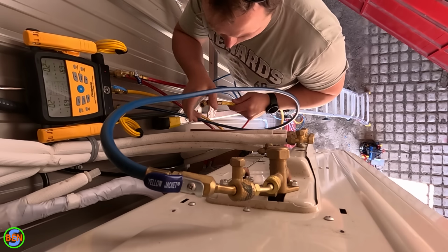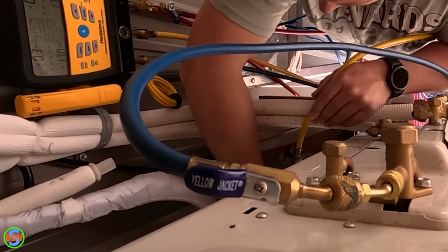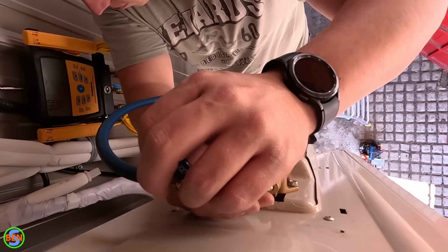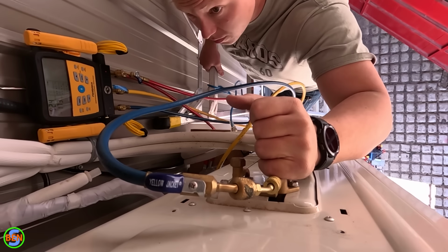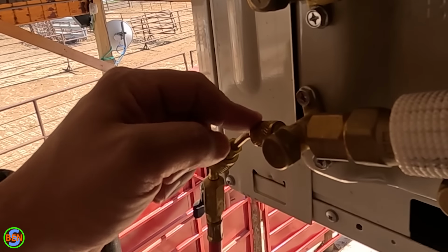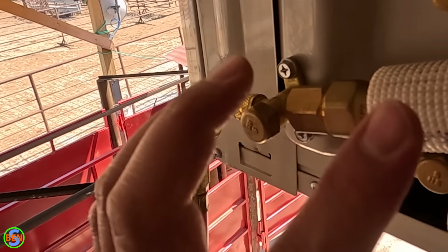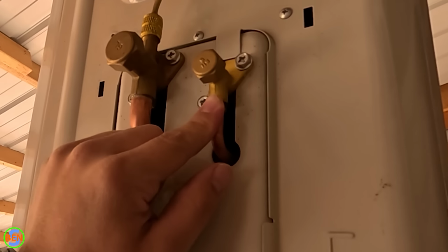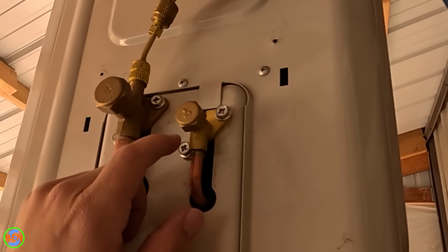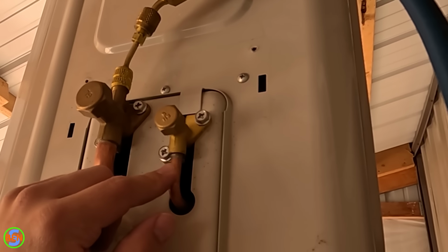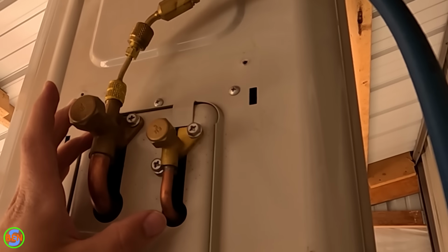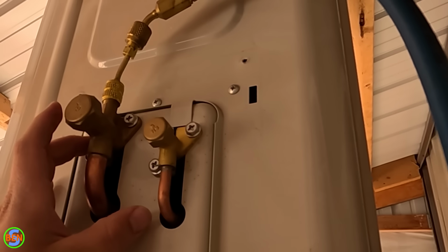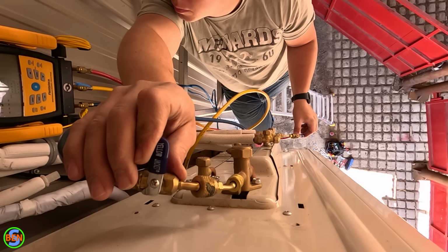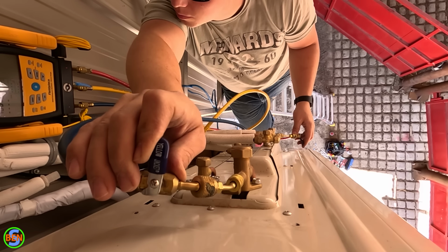So when you hook up your gauges, you're going to want to take the yellow hose and connect that to your vacuum pump. And then the blue and the red hose, the high and the low side, oftentimes you can connect both of those to a traditional system while you're pulling a vacuum. This one was set up more so to just pull a vacuum on the low side by itself, and we could have just done that with just the blue hose, but I actually decided to hook up both the blue hose and the red hose just as two separate ports on the low side. There aren't really access ports to the high side as much on a mini split, because it's not really designed for you to be able to just throw your gauges on there and check the pressure. The system is more sophisticated than that, and if you lose some refrigerant, you're probably going to have to actually take all of it out and weigh it back in again. I chose to connect both the low side hose and the high side hose to the low side of the system in order to be able to pull the vacuum a little bit faster.